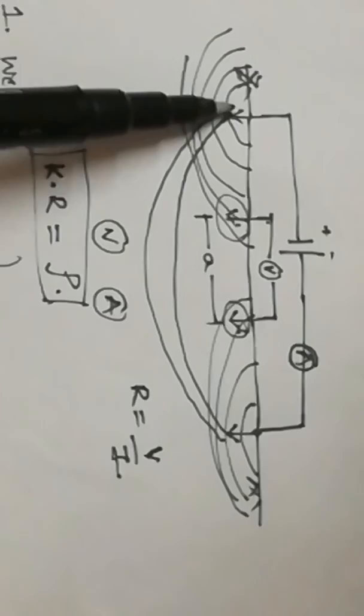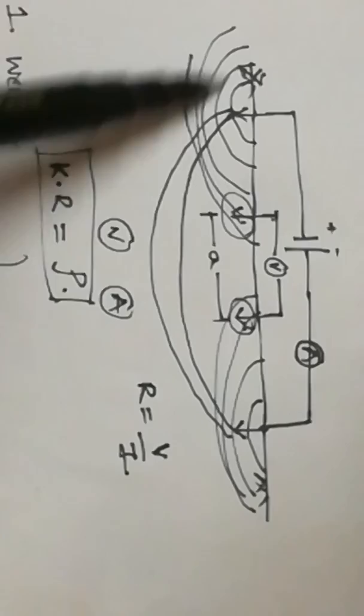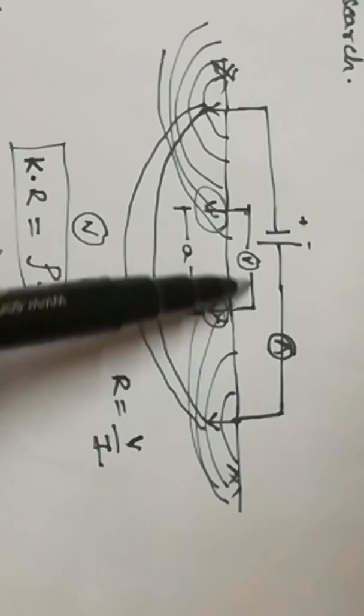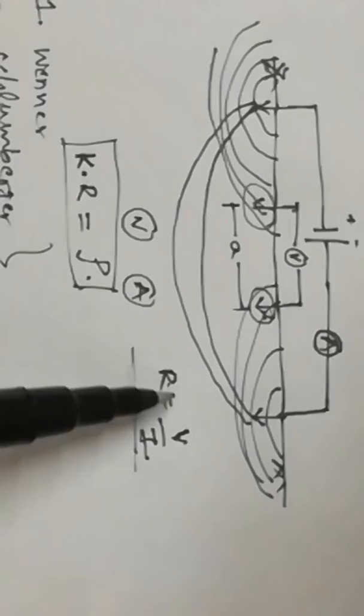When we pass current in the outer two electrodes, the current waves pass from one electrode to the other. Due to these current sources, equipotential lines are generated, and there is a generation of potential difference in the inner two electrodes. So from the inner two electrodes we get voltage, and from the outer two electrodes we get current. From Ohm's law, R equals V divided by I, giving us the resistance offered by the soil.